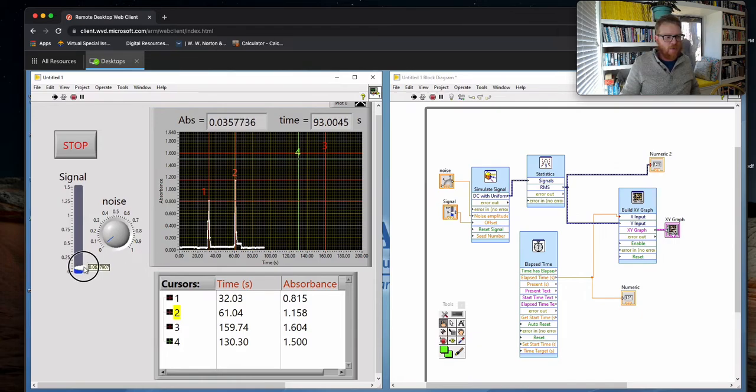Let's suppose we get one nasty slow thing coming off, which maybe then you can say, oh wait, it's not all the way out of there yet. Okay, now it's going. For a peak like this, maybe you would want to know the peak area, certainly, but at least as far as your initial diagnostic, you've got it right there in the chart. I didn't put in any kind of save or export of the data, but in principle, we should be able to take the XY data and send it directly into a file saver like you've done before.